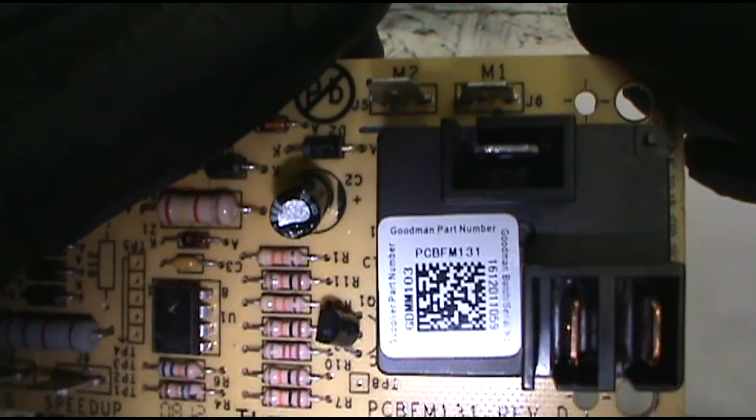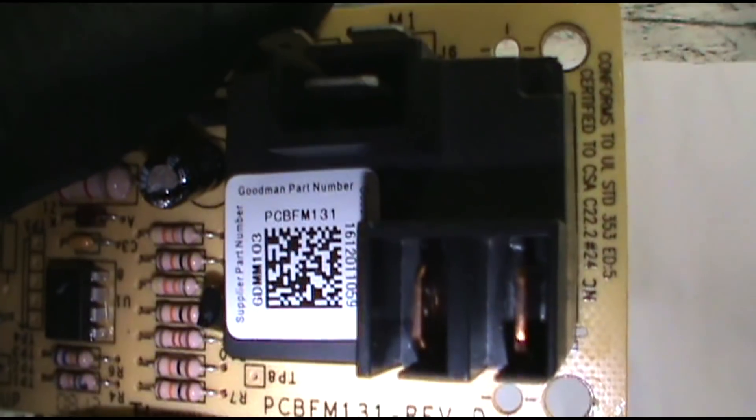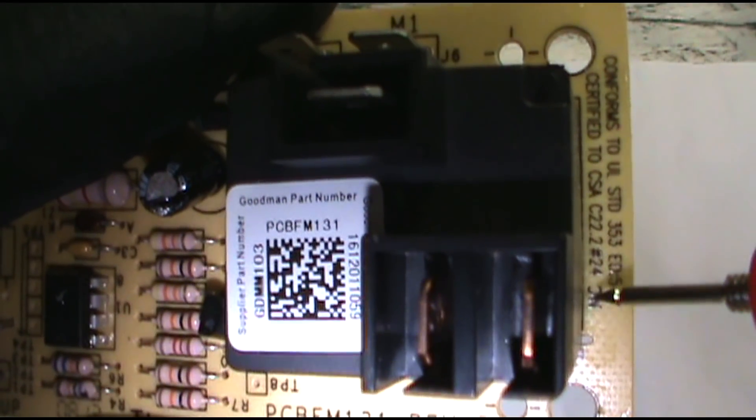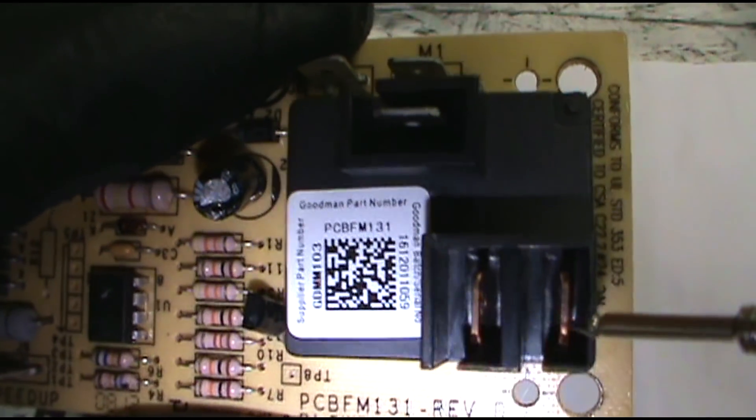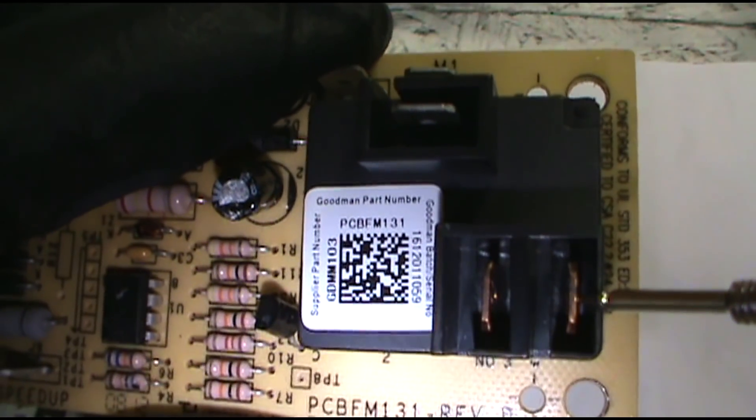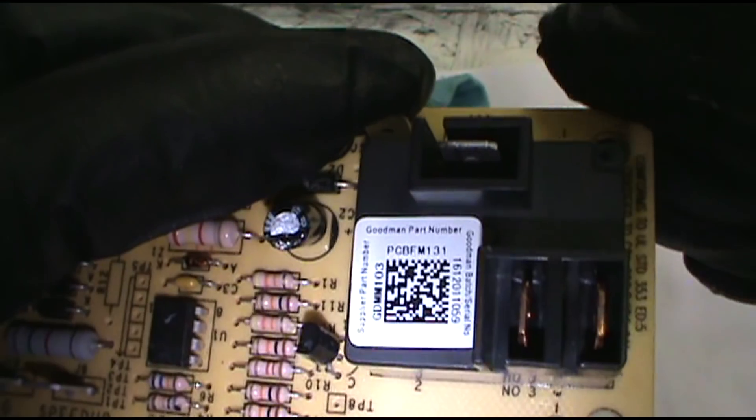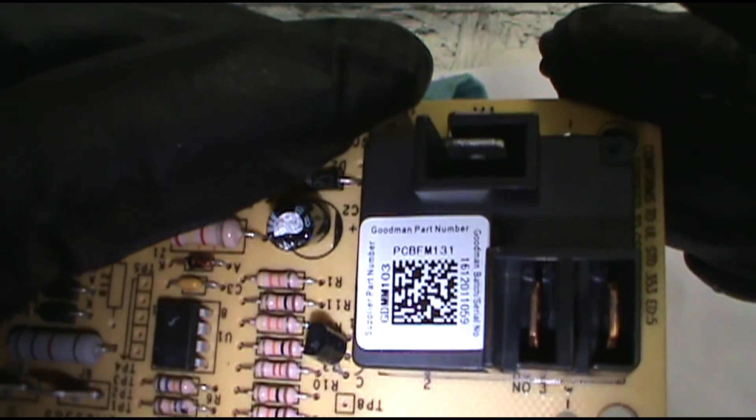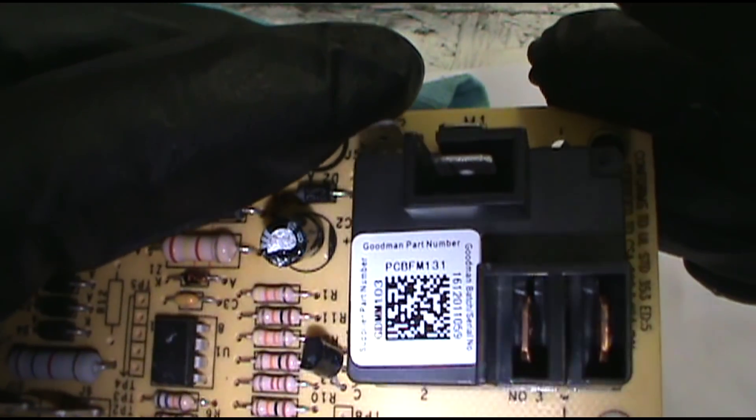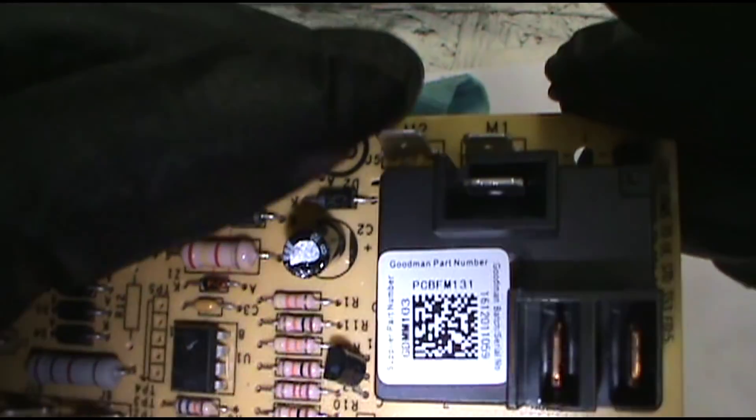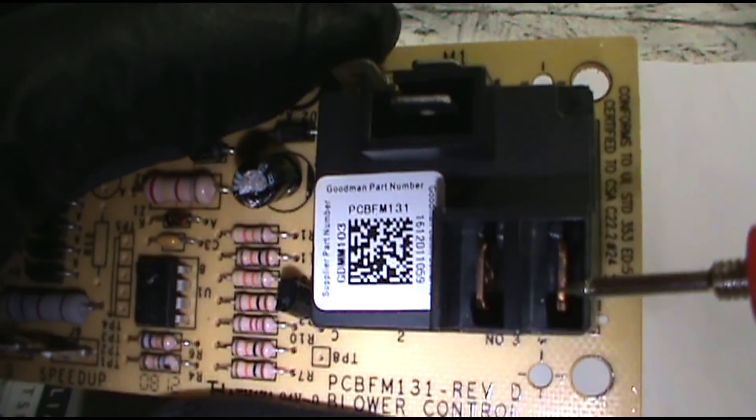And this NC here stands for normally closed. And this will be coming off a heat sequencer. It's a safety measure, so if the sequencer, you know, if the heat strips kick on but the blower, the fan motor doesn't come on, this will cause it to come on just to keep from burning the apartment down.